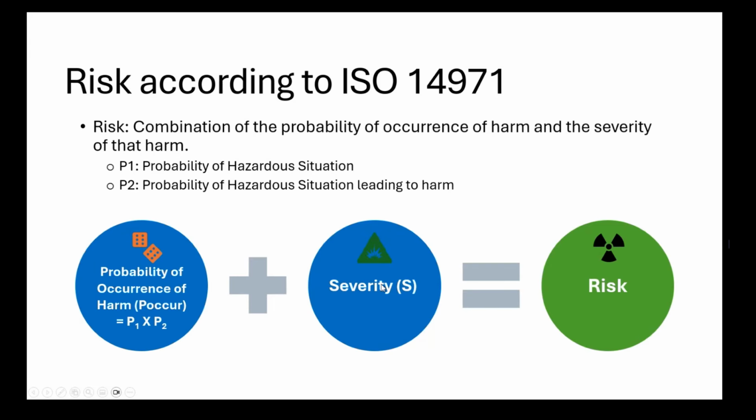Severity at a high level is how severe your risk or hazard is. For example, if you have a spectrum ranging from negligible all the way up to catastrophic, 5 scale numbers I've seen most of the time. And this is where negligible means it's going to be just like customer or user annoyance. Catastrophic is where there could be a death involved. And then there are intermediate rankings as well, like minor, critical, moderate. This is where the patient could have various different types of implications from the patient safety perspective.